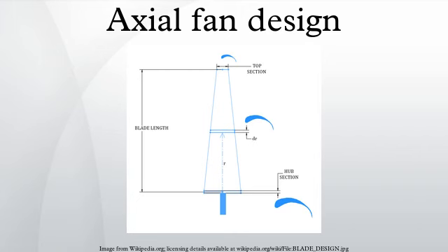Methods to avoid unsteady flow: by designing the fan blades with a proper hub-to-tip ratio and analyzing performance based on the number of blades so that the flow doesn't separate on the blade surface, these effects can be reduced. Some of the methods to overcome these effects are recirculation of excess air through the fan. Axial fans are high-specific speed devices; to operate them at high efficiency and minimize the effects, they have to be operated at low speeds. For controlling and directing the flow, use of guide vanes is suggested.